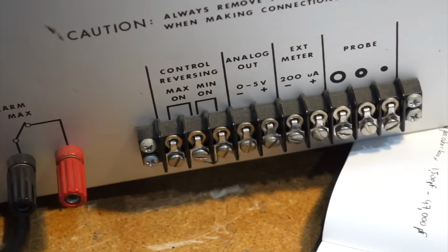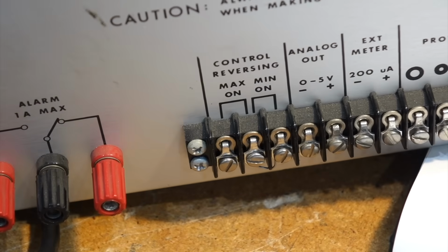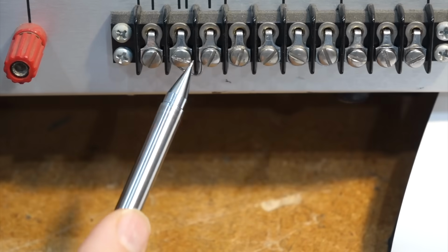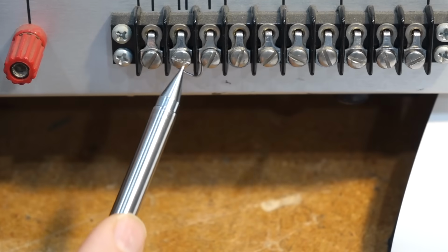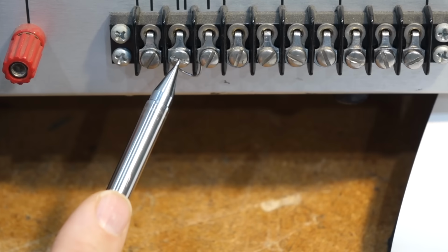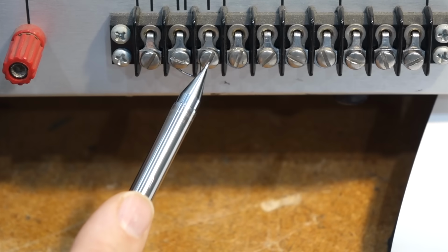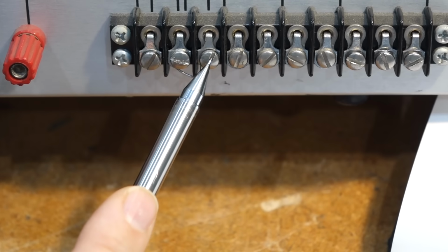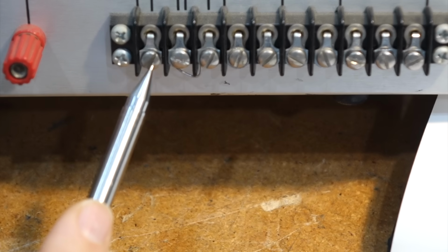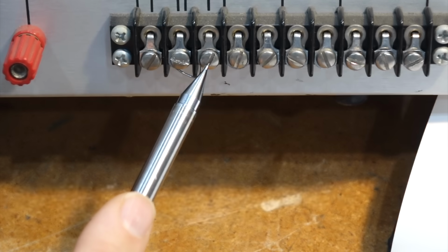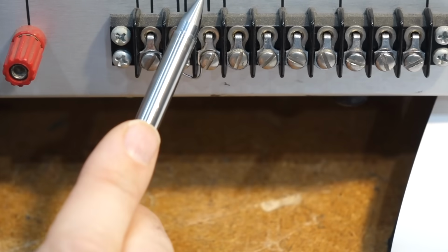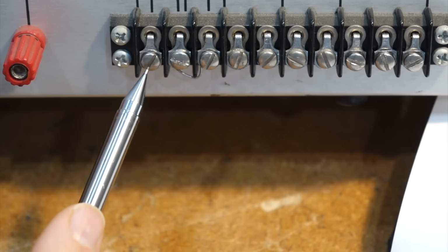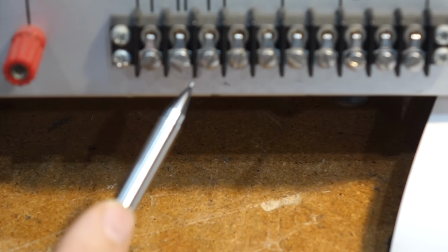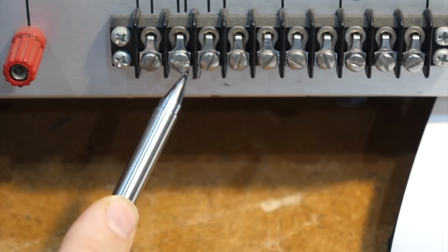It says control reversing. And what happens is that you need a jumper between this and that, or this one and here. But this goes to the coil of the reed relay, and this goes to one of the flip-flop thyristors, and this is the other flip-flop thyristor. So right now I have it come on when it goes below min, and you can also have it come on when it goes above max. But if you have nothing there, absolutely nothing will happen.